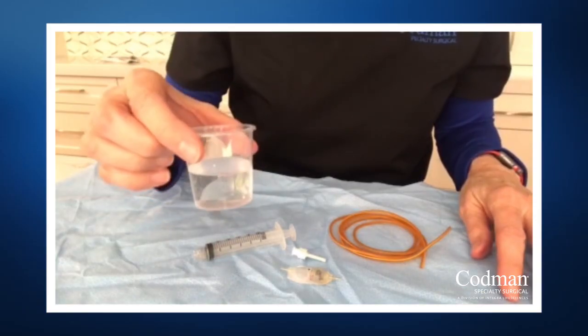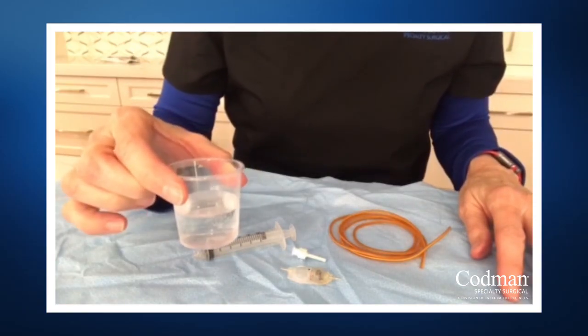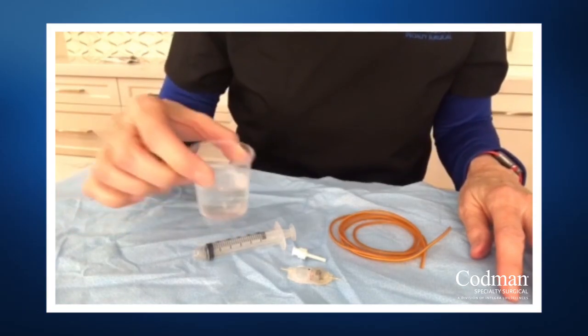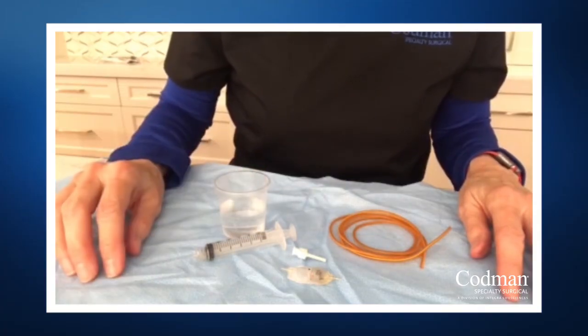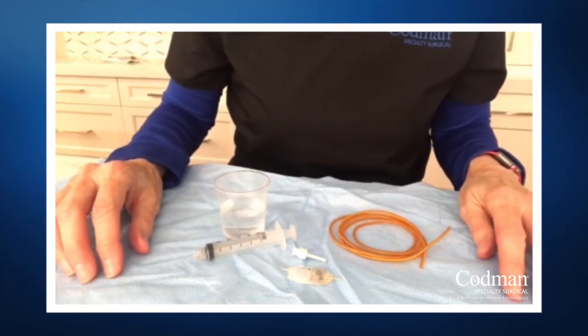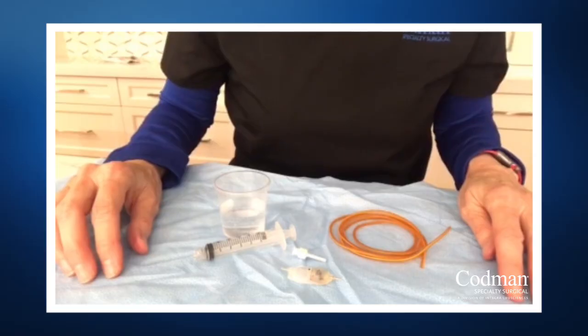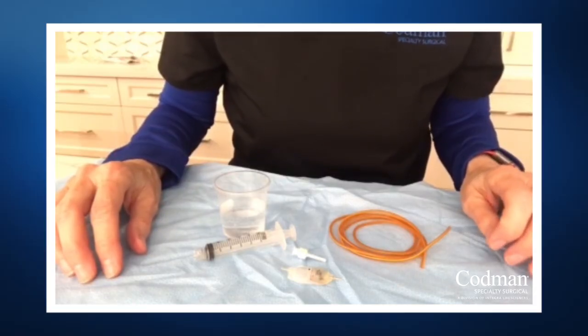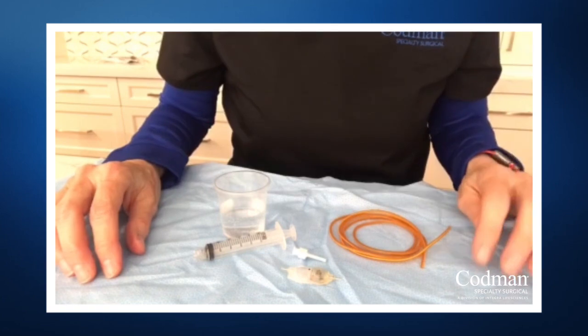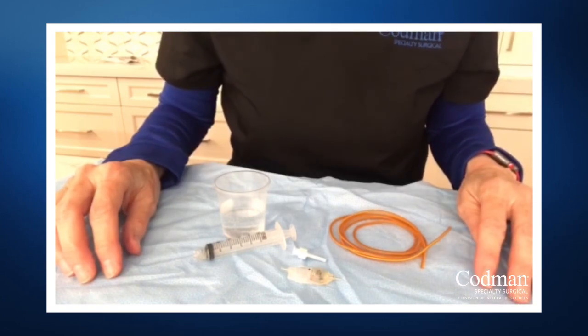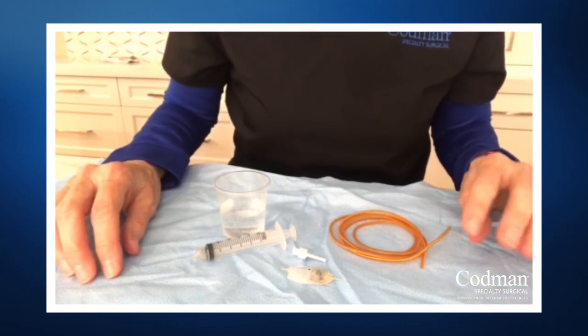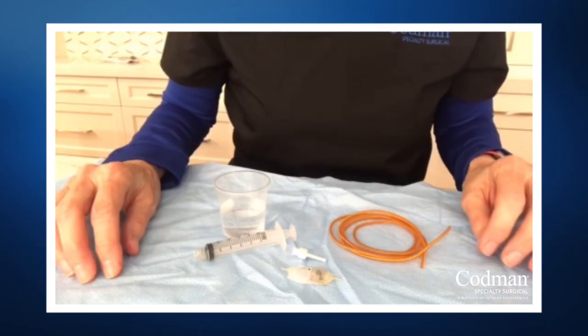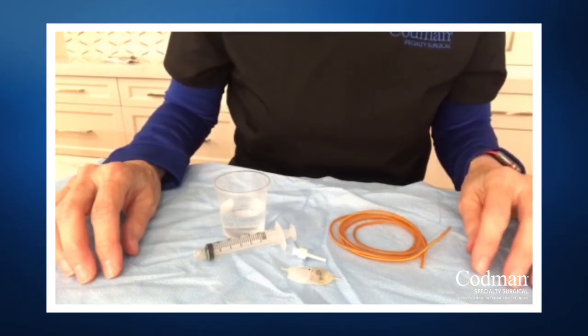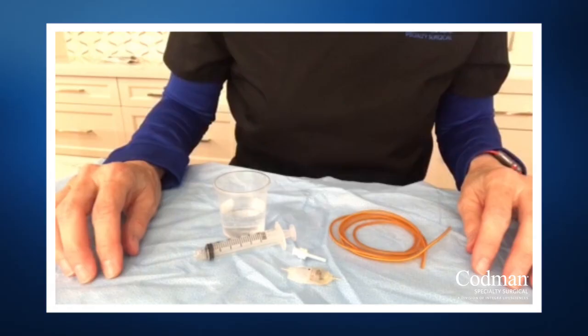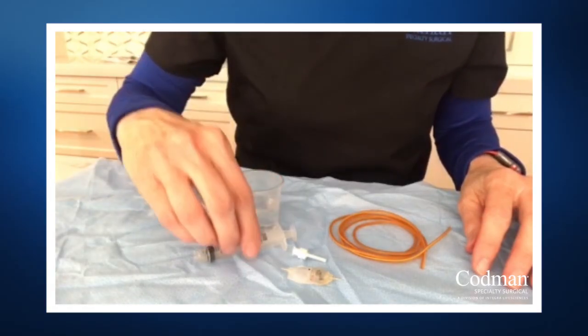And then you'll need some type of solution. Now this solution, if you're priming just the valve, can be an antibiotic solution with bacitracin or some other antibiotic solution. But it's very important that you don't fill, flush, or pump the valve in fluid in which cotton, gauze, or any type of other lint releasing material has been soaked. You don't want to introduce any foreign objects into the valve that could possibly occlude the valve once it's been implanted. So let's go ahead and show how to prime that.